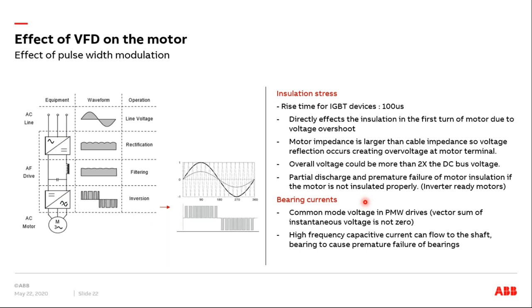We went to the grid side, but what are the effects on the motor side? And Deepak, you also talked about this a little bit before. So basically, we are talking about insulation stress and the bearing currents. As Deepak mentioned, while doing this inversion side, when going from DC to AC, that's when the motor is affected.